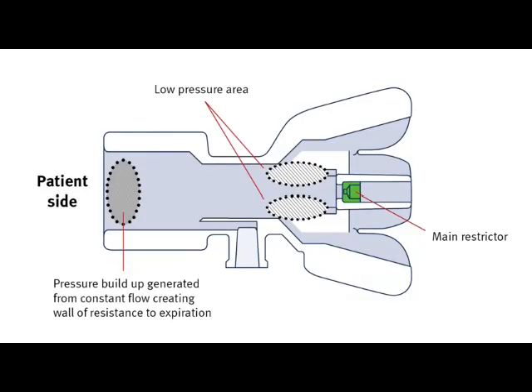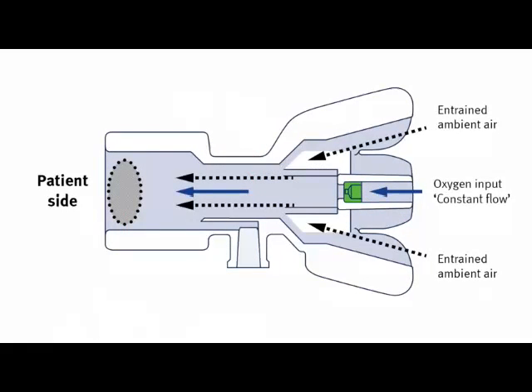This in turn causes the pressure to drop and allows for ambient air to be entrained into the chamber and mixed with oxygen. By varying the oxygen flow through the vectored flow valve, the baseline pressure can be raised or lowered to maintain a constant airway pressure.